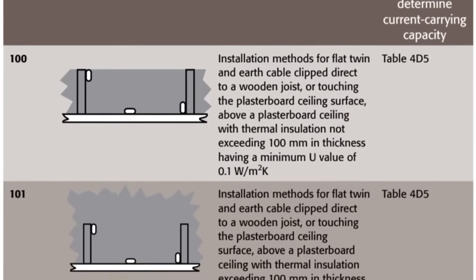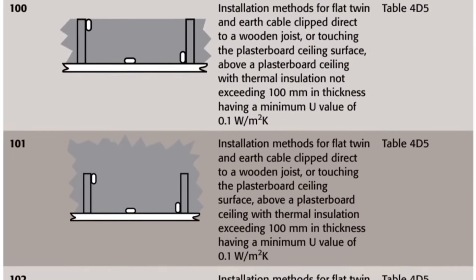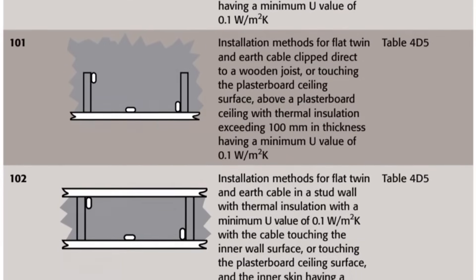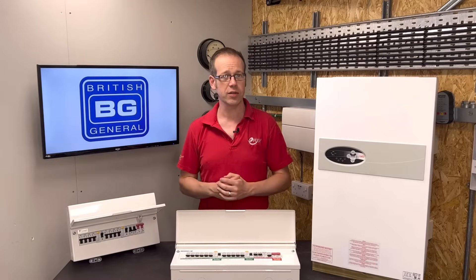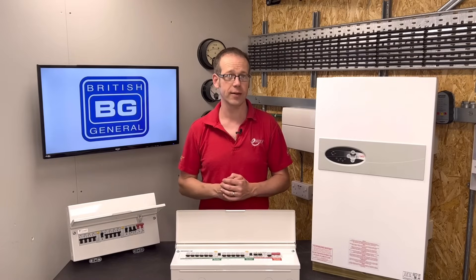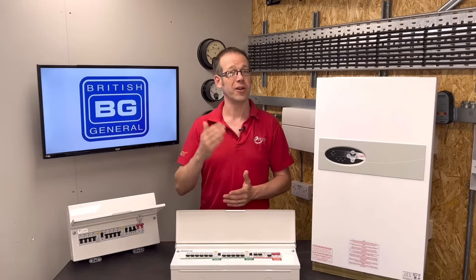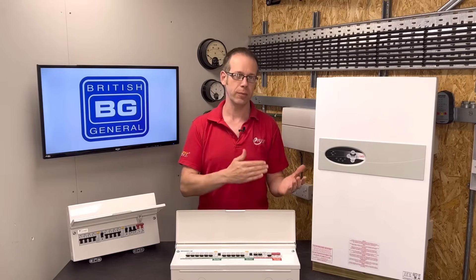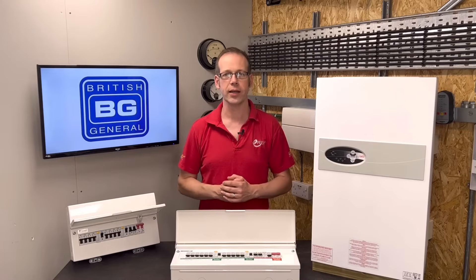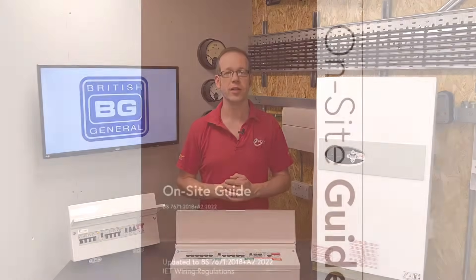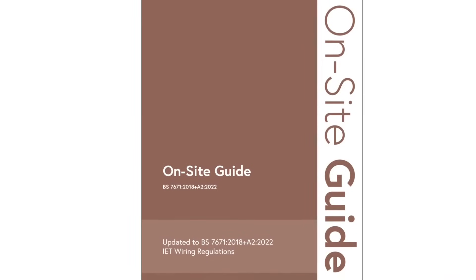How much current the cable can handle is directly related to how it's installed. To figure out what size of cable to install, we may need to take the factors we've just mentioned, as well as some others, in order to rate our cable. We refer to these as rating factors — you may hear some people call them correction factors because that's what they used to be called in older editions of the regulations. We find them in various documents but for now we'll stick to the ones in the on-site guide.